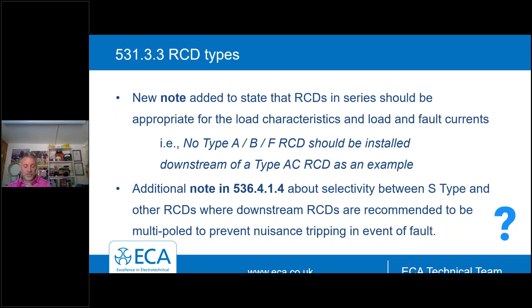There's a recommendation, especially where you've got TT earthing systems, to consider multi-pole devices, because they will disconnect the neutral to prevent nuisance tripping in the event of a fault. This is just clarifying really good engineering.